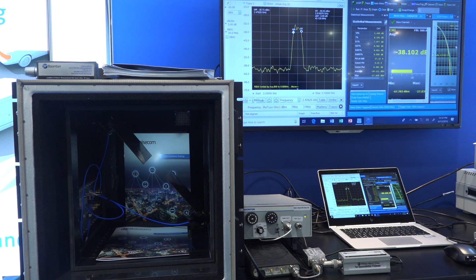Here we have a noise source on the right, and this is an over-the-air measurement, injecting a 40 megahertz wide noise into a 2.5 gigahertz antenna, and capturing that through another antenna. This is a setup you'd use for over-the-air calibration, and their noise sources are capable of doing that. What's interesting is that the power meters placed on the right side have the ability to capture instantaneous power as well as average power.